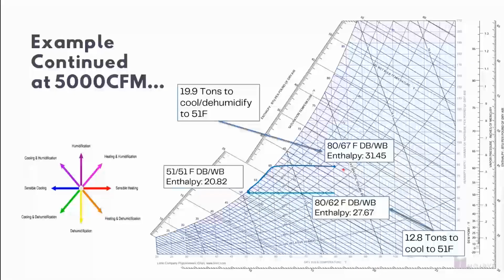5,000 CFM? You're going to do cooling. And once you hit your saturation curve, you start doing dehumidification, which takes work and energy to hit your final target condition of 51 degrees. If you provide drier air, you wind up being in a situation where you don't condense any moisture on a coil. So you're doing primarily, and almost in this case, all sensible cooling.